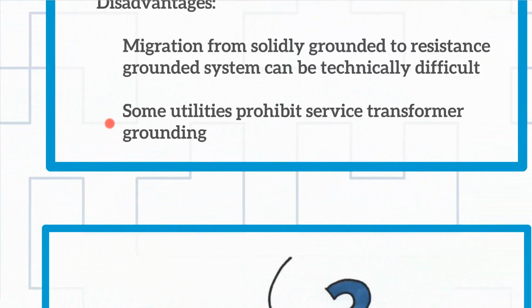Here's the problem with a power company. You're talking to the distribution part of the power company, and all they understand is solid grounding because they're normally used to feeding aerial lines, and they don't have cables. So if they get a ground fault in the line, it arcs through the air, a tree limb hits it, and then the recloser opens, and then falls off, and then they close it back in, and they've got new insulation called new air, and it's the cheapest way they do it.